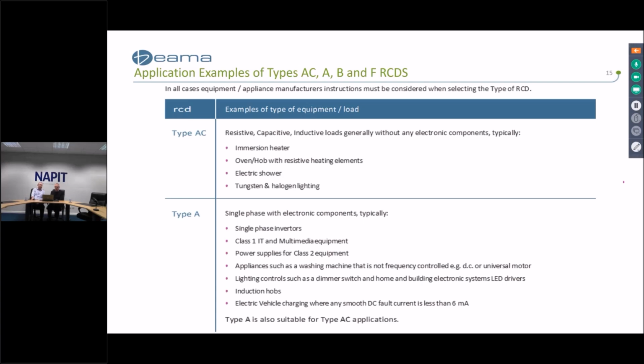Type A RCDs are suitable for all of the Type AC applications, but with the addition of being suitable for more sophisticated technology utilized in some modern appliances. The appliances are as listed, and they include single-phase inverters, Class 1 IT and multimedia equipment, power supplies for Class 2 equipment, appliances such as washing machines that are not frequency controlled, e.g. DC or universal motor, lighting controls such as dimmer switches and home and building electronic systems, LED drivers, induction hobs, electric vehicle charging where any smooth DC fault current is less than 6 milliamps. And as stated before, Type A is suitable for all of the Type AC applications.